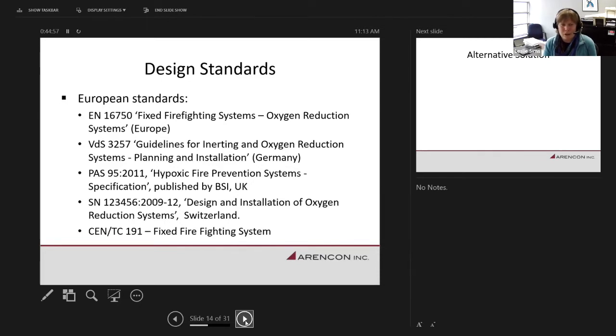I think the starting document was the VDS 3257, because it was the Germans, Wagner's a German company, and they are the early developer of these systems. So they developed a guideline for the inerting and oxygen reduction systems. It's a combination of a standard and a ULC listing requirement. So the VDS certification covers components. It covers the testing criteria to set the ignition thresholds, and it gives you the installation design criteria for number of sensors, concentration levels, safety levels. It also requires certified installers and sign off and commissioning.